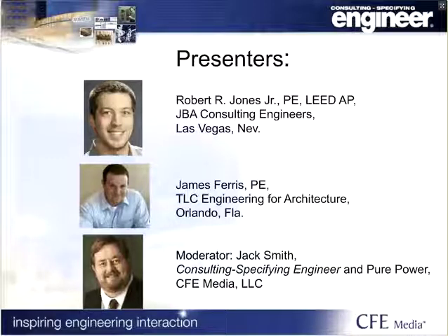Okay, we have time for probably one more question. Rob, I'm going to give this one to you. One of our viewers would like a little bit of extra explanation about the difference between prime and continuous. I think that was on my slides, actually. Continuous is, I have a 1500 kW generator, and I'm running absolutely 24/7 at that rating, and it's available all the time. It's basically I would be running off of that as my primary source almost. Prime power, the load does vary a little bit, and the derating of the generator is not as much typically. So it would vary a little bit on that load for prime power.